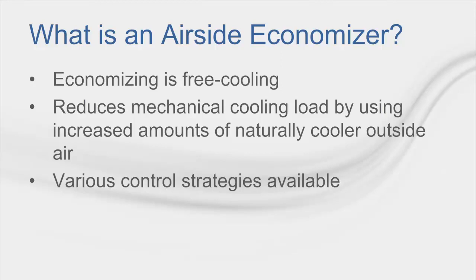The method required may be dictated by local building codes or by Section 6.5.1.1 of ASHRAE Standard 90.1. Additionally, when applying an airside economizer, building pressurization can become an issue with the introduction of this additional outdoor air. As such, Standard 90.1 requires the use of a relief system to prevent overpressurization.